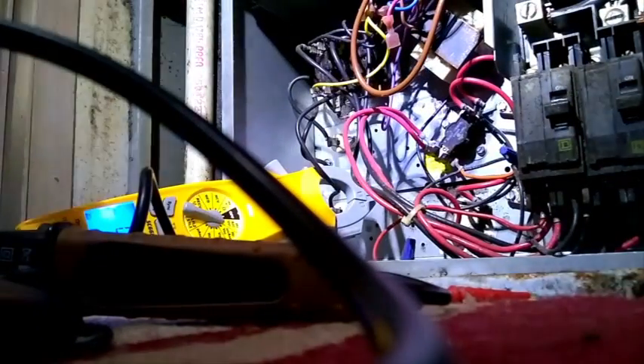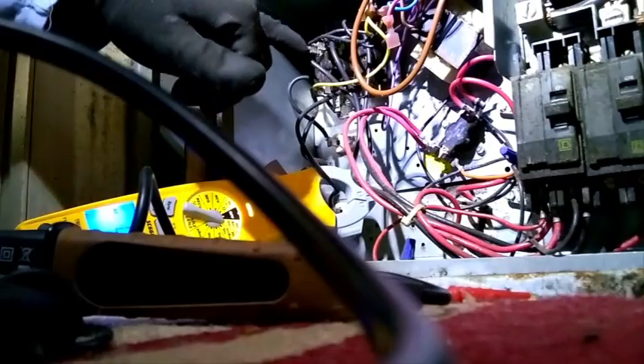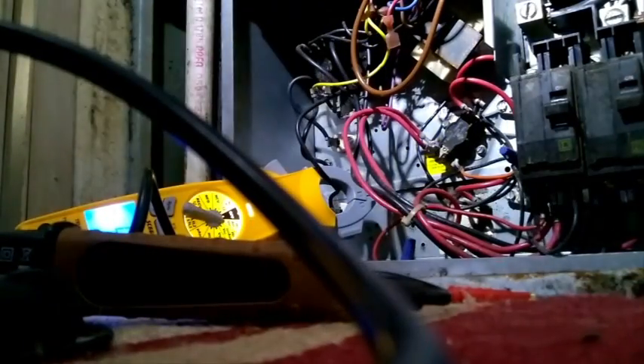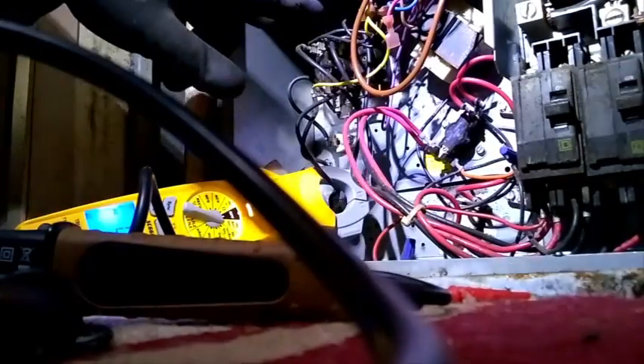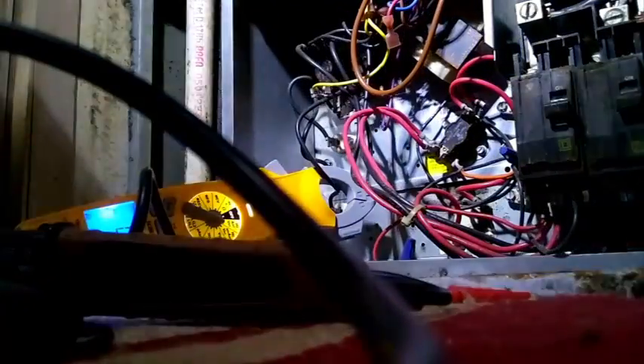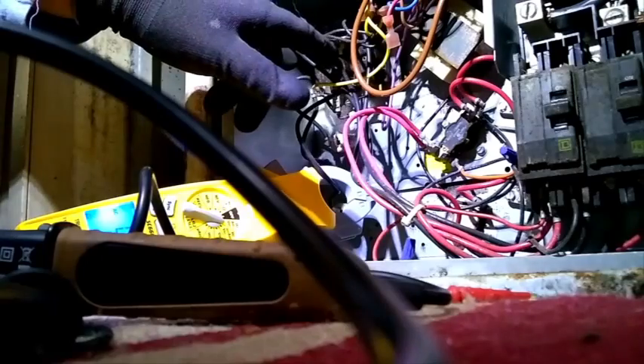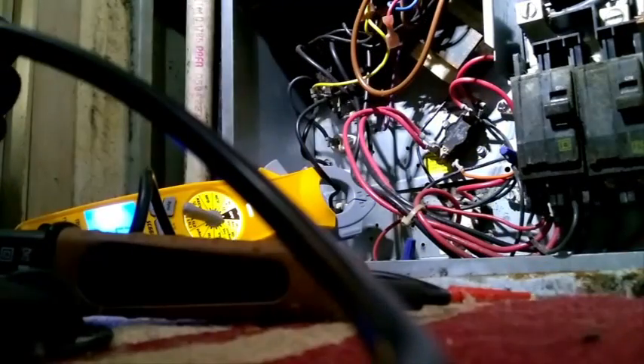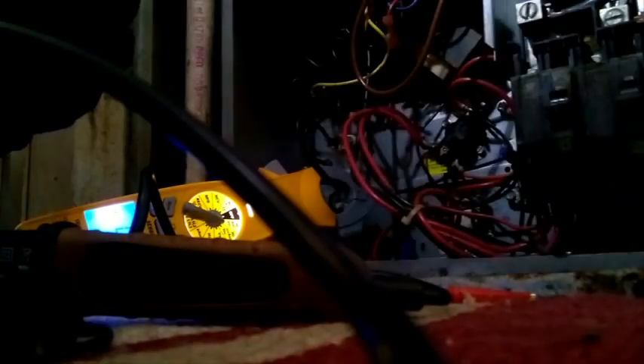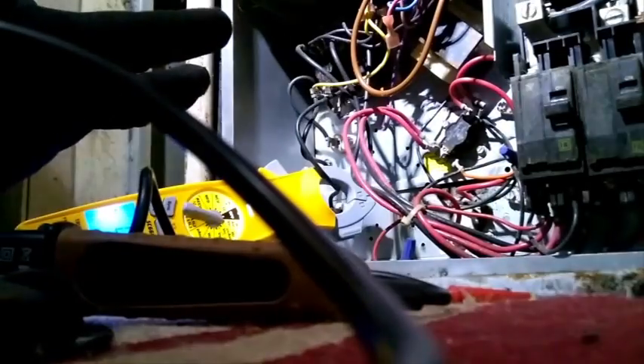There's two little relays down here at the bottom, and they turn on your heating elements. When they get power from your thermostat, it comes in on these wires, travels down here, and tells these relays that they need to close and put power on the elements. There's two of them because you have 15 kilowatts of heat in this furnace, and there's two different relays—one controls half of it, and one controls the other half.